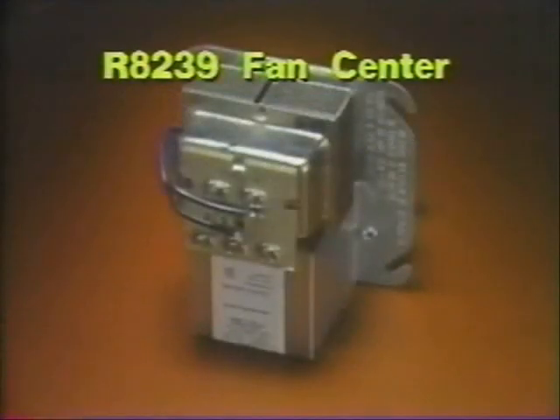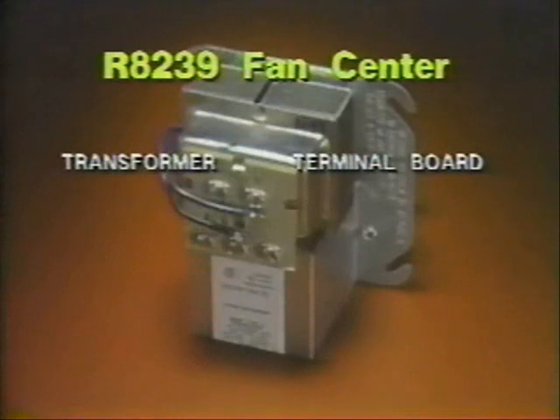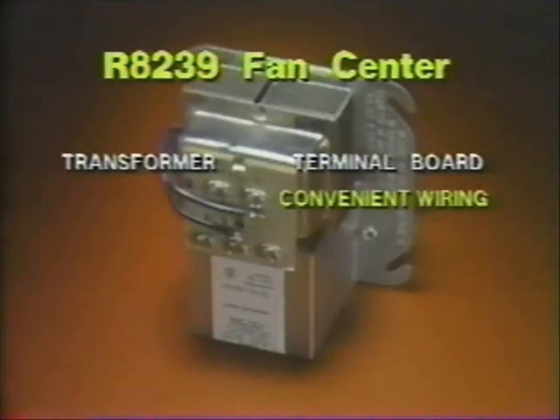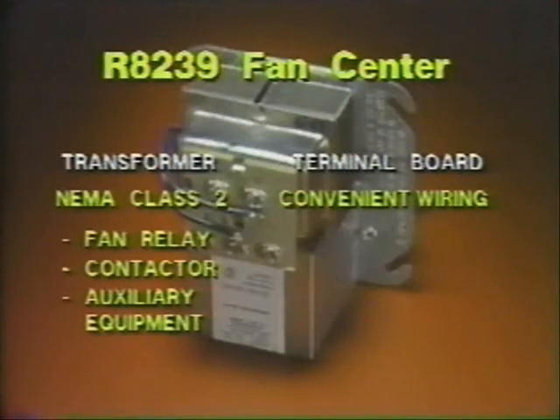Honeywell's R8225 is a fan relay designed to provide low-voltage control of line-voltage fan motors and auxiliary circuits in cooling, heating, and commercial refrigeration systems. The R8239 fan center performs the same switching functions as a fan relay, but in addition, it has a transformer and a terminal board for convenient wiring of the low-voltage system. The transformer meets the NEMA standard for Class II transformers and is big enough to power the fan relay, the compressor contactor, and the controls for auxiliary equipment in most systems.